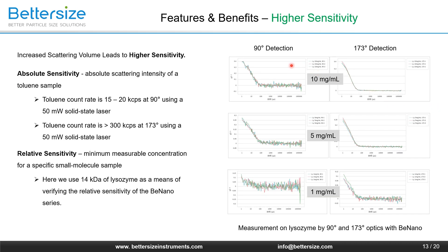Another important feature of the backscattering technology is the increased scattering volume, which leads to higher sensitivity. Two types of sensitivities are usually used for DLS analyzers. One is absolute sensitivity, defined as the absolute scattering intensity of a toluene sample. With a 50-mW solid-state laser, the toluene count rate is 15 to 20 kilocounts per second (kcps) at 90 degrees, whereas the toluene count rate is more than 300 kcps at 173 degrees. In terms of absolute sensitivity, backscattering optics is at least 10 times as sensitive as the 90-degree optics.